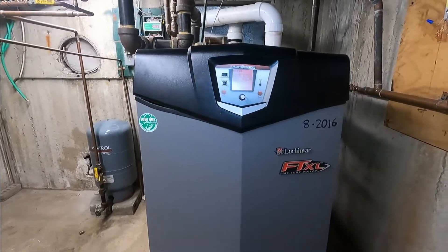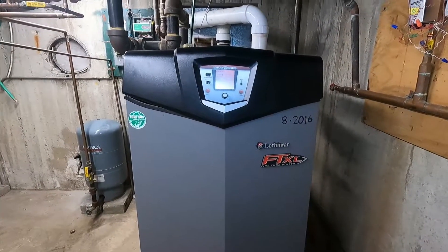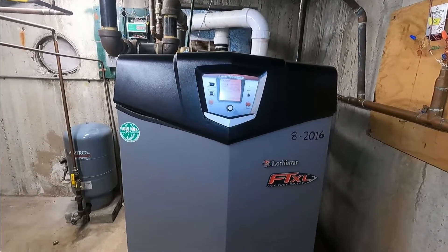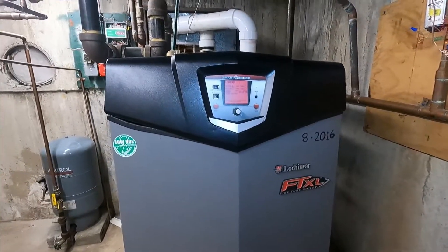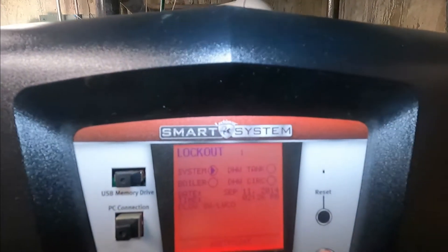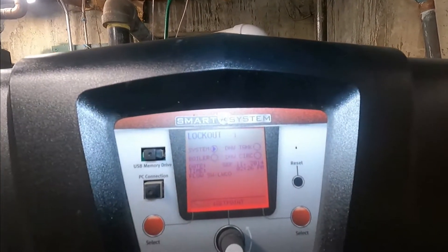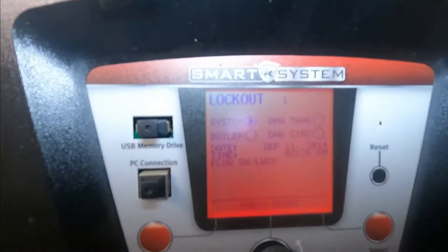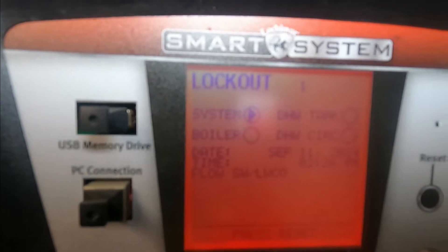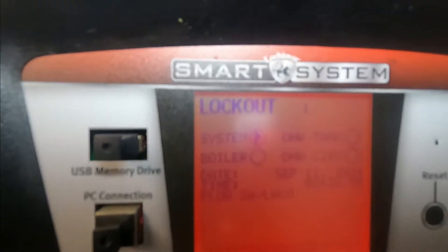We have a Lochinvar FTXL boiler — it's 400,000 BTUs. It serves 12 apartments and it has a lockout. It's going to be hard to see, but it's a lockout and it says flow switch or low water cutoff. Can you see on the screen? So it's a flow switch or a low water cutoff.